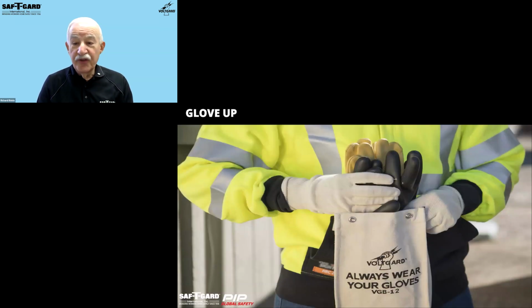Rubber insulating gloves are manufactured using proprietary materials and manufacturing processes with 100% testing to provide the highest level of protection. That's an AQL that's off the charts. 100%, every product after manufacturing is visually inspected and electrically tested before it leaves the manufacturing facility. To be effective, those rubber insulating gloves must incorporate high dielectric and physical strength, along with comfort, flexibility, and durability. Because if they're not comfortable and flexible, workers are not going to wear them, and that's going to increase the risk of injury or death. To help ensure safety and performance, rubber insulating gloves must meet or exceed the requirements of ASTM standard D120, which is the standard specification for rubber insulating gloves and is enumerated specifically by name and number in the OSHA standards.